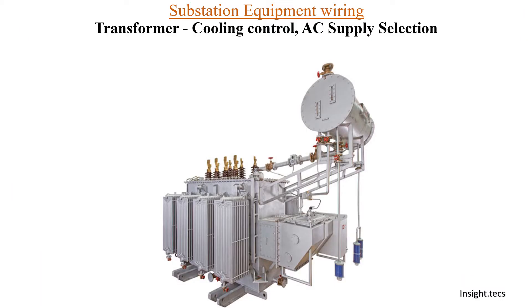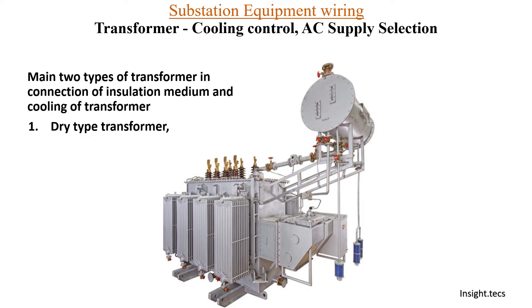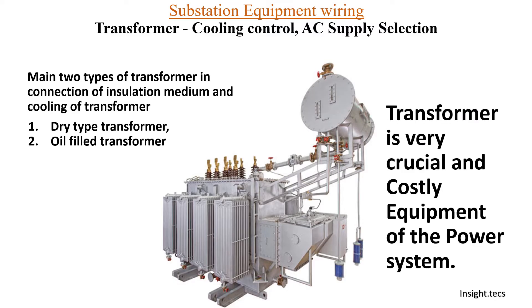Continuing in today's video about substation equipment wiring, specifically we are going to learn about cooling control AC supply selection. In the previous video, we have seen that there are basically two types of transformers — dry type and oil type transformers. For oil type transformers, we have seen different kinds of cooling systems. As we know, the transformer is the most crucial and costly equipment, so taking care of its cooling is very important.